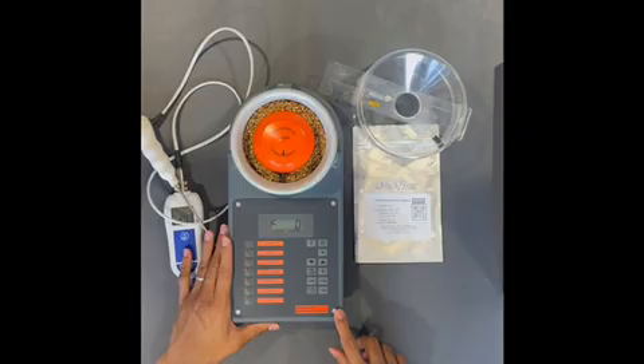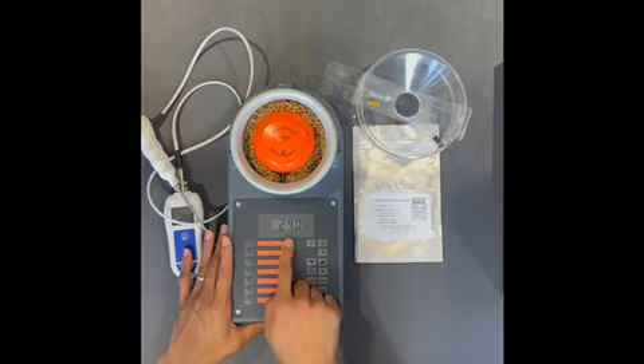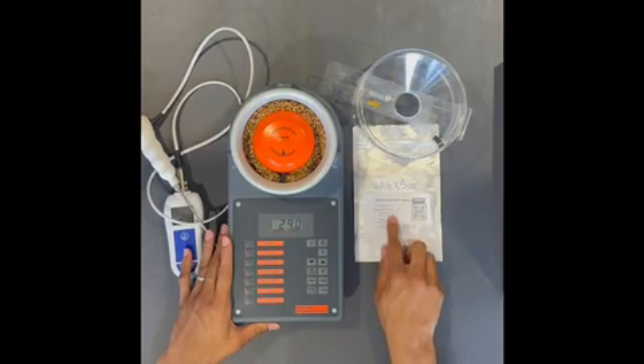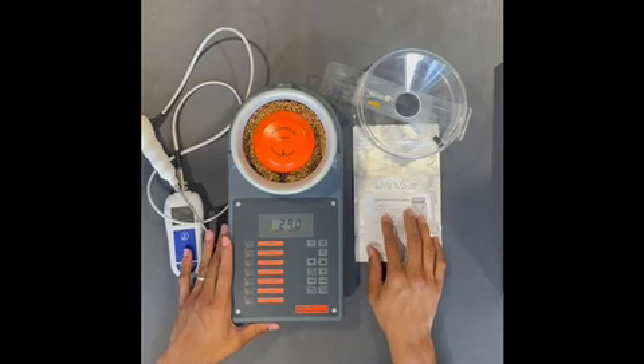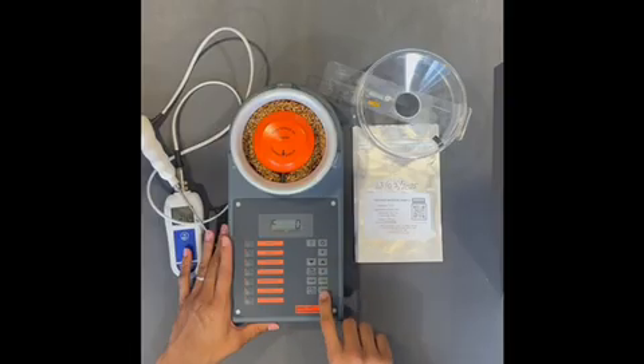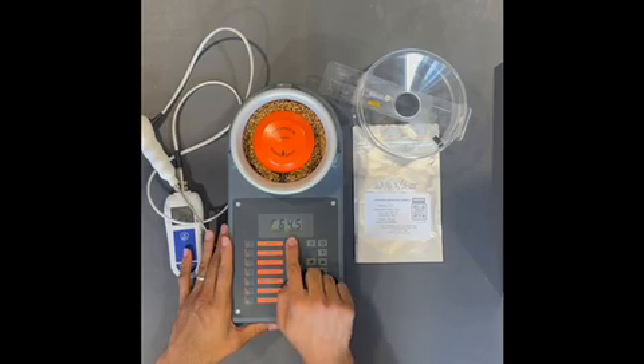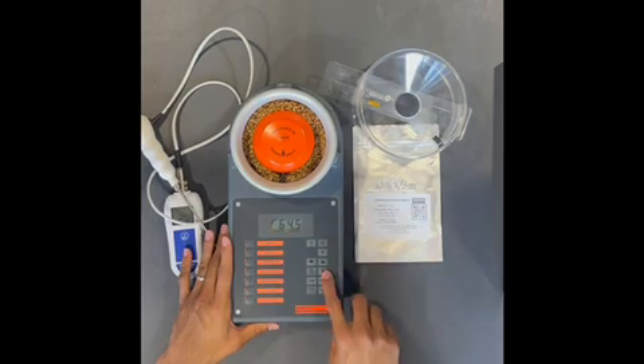press 0 and H2O, which should give us a reading of 29, which matches the capacitance value of the sample bag. We then want to go ahead and press 0 again and kgHL, which should give us 64.5, which is 180 grams. We then want to go ahead and press 0 again, temperature.